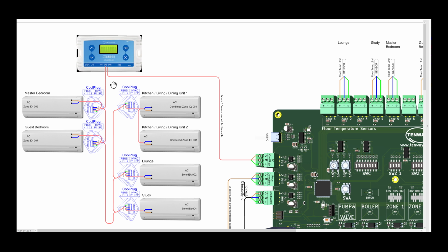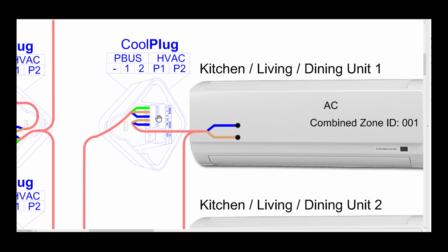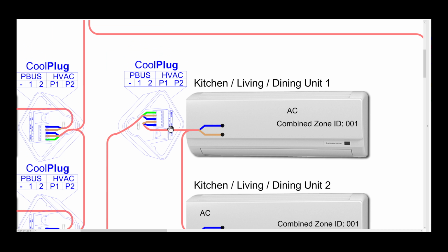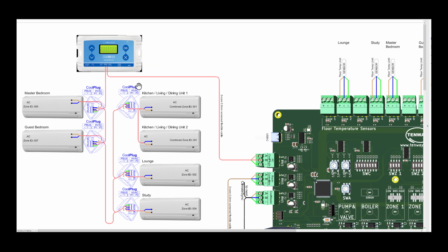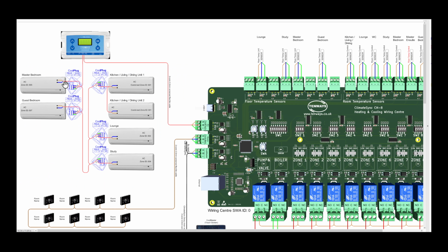So we can see over here in this wiring center that for the dining room unit they have 2 indoor units. The 2 indoor units are daisy chained on the indoor connection back to a single CoolPlug, and the CoolPlug is then wired to the cooling hub, and we can see over here also the connections. From the indoor unit it goes on this specific unit on P1, P2, as it's a Daikin controller and it's a Daikin CoolPlug. And we have the Modbus daisy chain that goes from the P-bus to the P-bus on the cooling hub. So this is the communication with the AC units. Again, the cable will be a 2-core 0.5 millimeter screened cable.